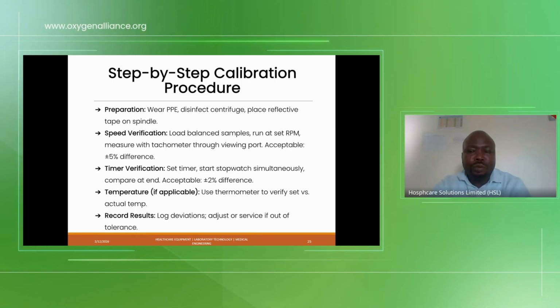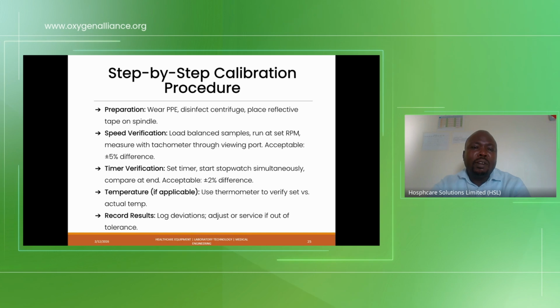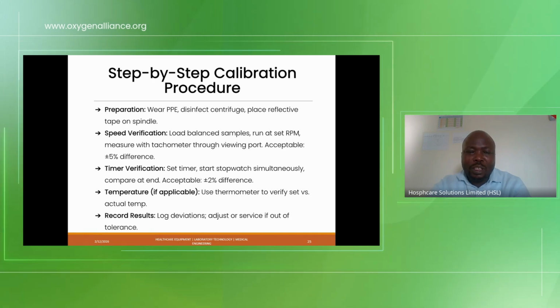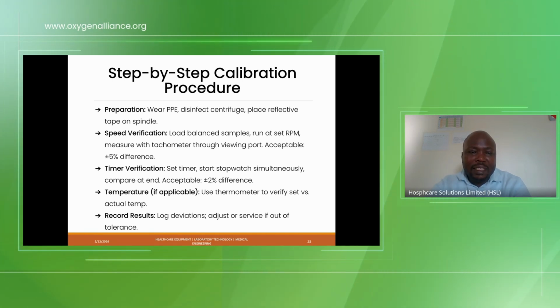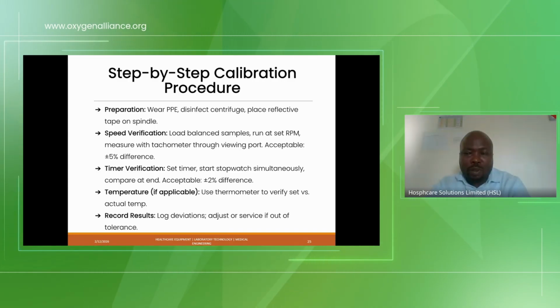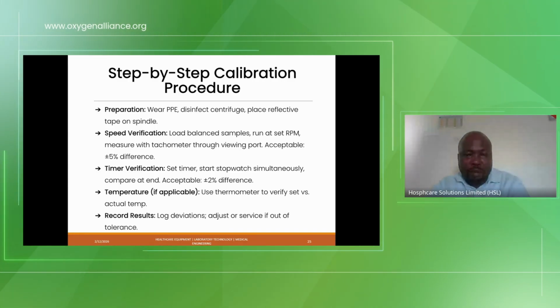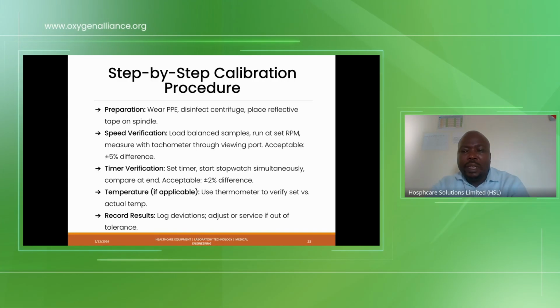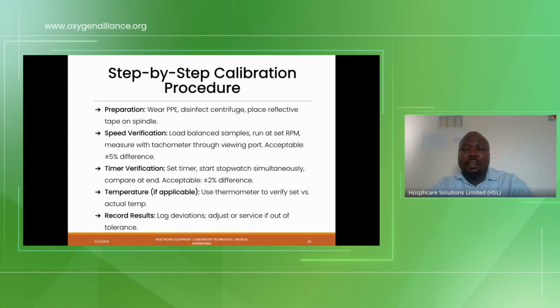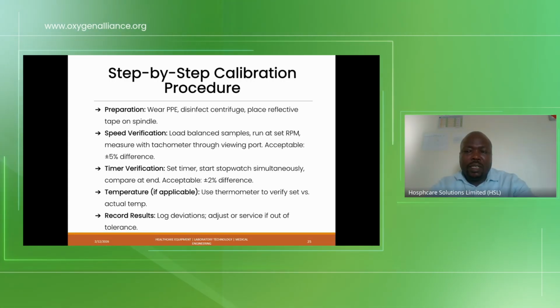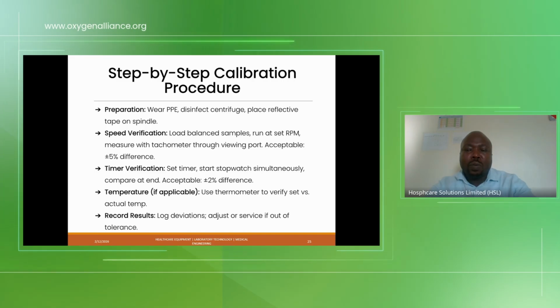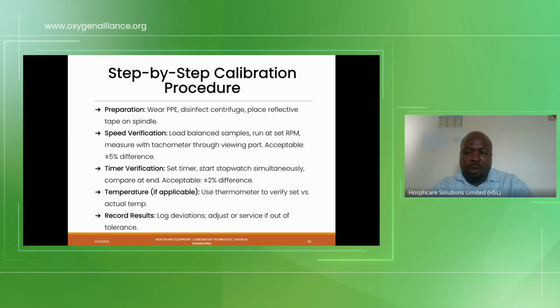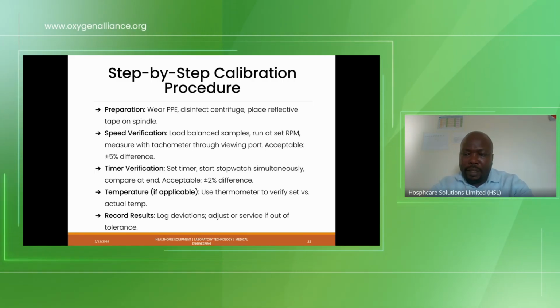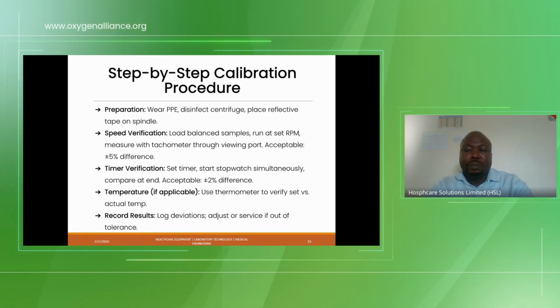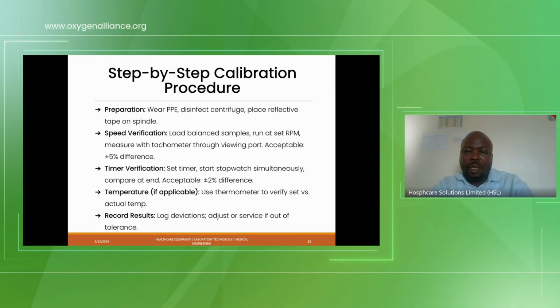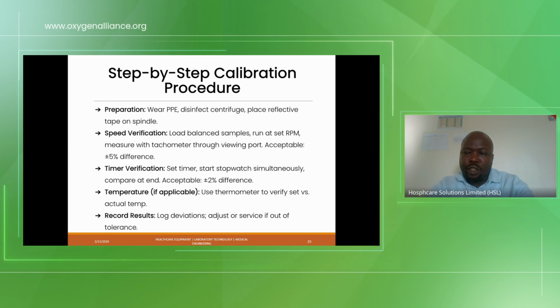by using a stopwatch. So get a calibrated stopwatch. Even your stopwatch needs to be calibrated. You don't calibrate the timer using an uncalibrated stopwatch. You choose a test run time, for example, 5 minutes. You need to run the centrifuge. You start the centrifuge and the stopwatch together concurrently. You compare the readings, check the centrifuge display time, and at the same time, you monitor the stopwatch.